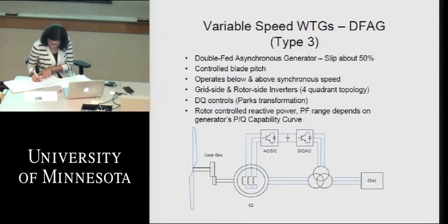This is a commonly used design. It uses a double-fed asynchronous generator. It's often called a DFAG, a double-fed induction generator. But in all reality, it doesn't work off of Faraday's laws of induction. We actually have a rotor excitation control, not just like in the Type 2 where we increase or decrease the rotor current. Here we can actually control its magnitude and its phase relationship between the current and the voltage. And as such, we have vector control of the rotor current. So we use this double-fed asynchronous generator, and what does it do? It increases the slip capability up to about 50%.